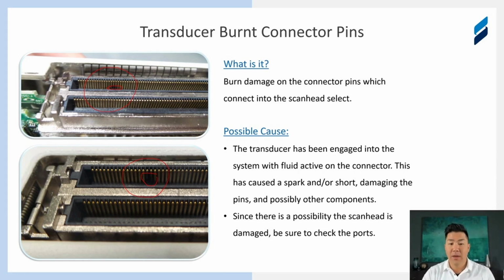This can become a real issue really quickly, because not only is the probe damaged, this could actually damage the machine as well. When that shorting happens, the circuit shorted together with the probe and the machine working together, they're connected. Those two circuits are connected, not only the probe side, but now the system side as well. So I highly recommend that if you see this, immediately go check the ports on the ultrasound machine to see if anything's going on there. This will absolutely cause catastrophic errors. It will cause noise. It'll cause anything under the sun that a probe or a machine can throw for an error. To reiterate, you have to check the system too and make sure that it's okay.